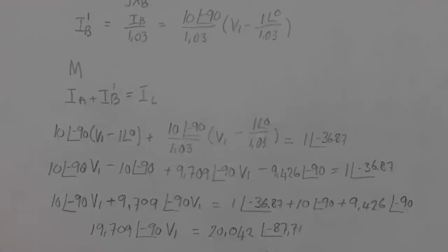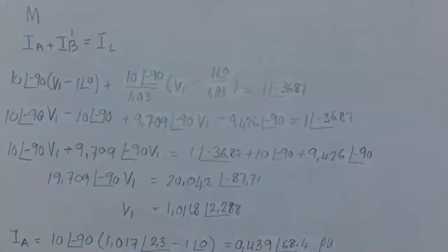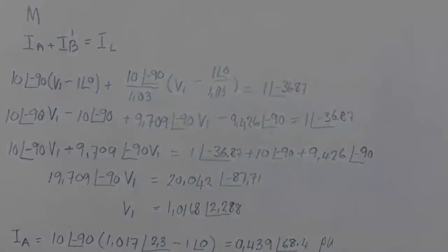Right, and then next week we are going to do the same things for an alternator. What happens if we change delta, and what happens if we change the excitation? And you will notice the same thing that happens here is going to happen with the alternator. If we change delta, we have a change in P. If we change the excitation, we're going to have a change in Q.